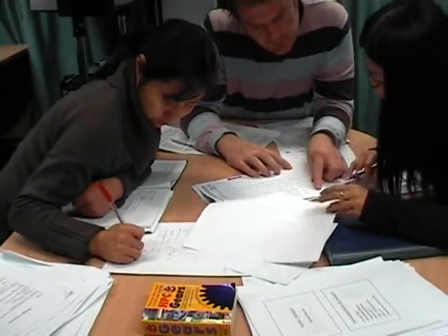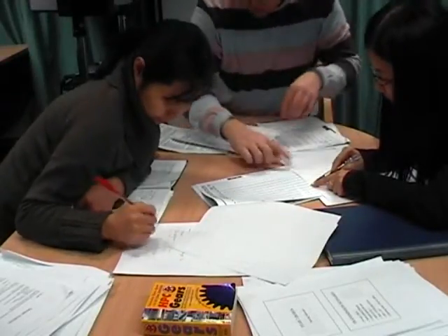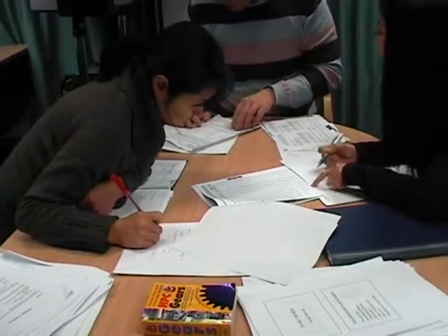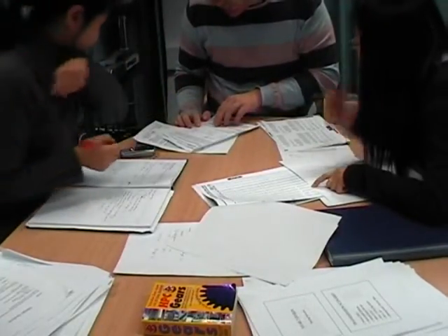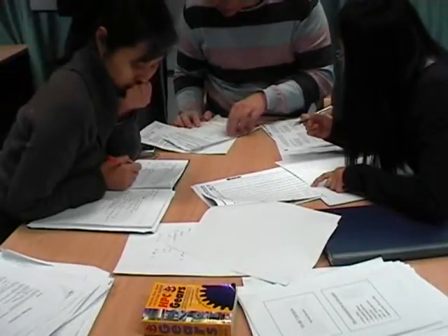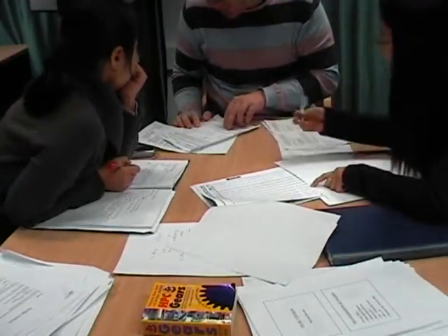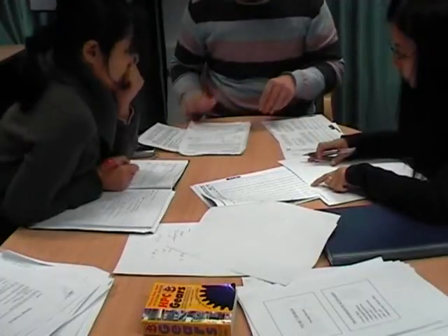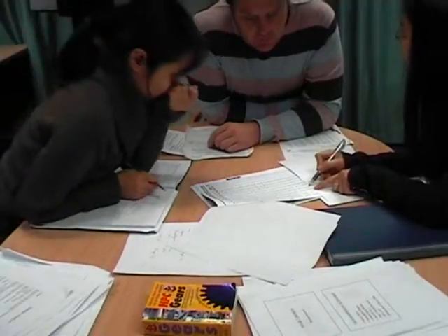So we have centre distance 507 or 587. We do have a tolerance on this. Note the above dimensions have a tolerance minimum of plus or minus 20 millimetres, in terms of the axial direction of bearing and pulley. Between the motor, pump and shaft it is plus or minus 50 millimetres. So we're 550, and either one would be okay.